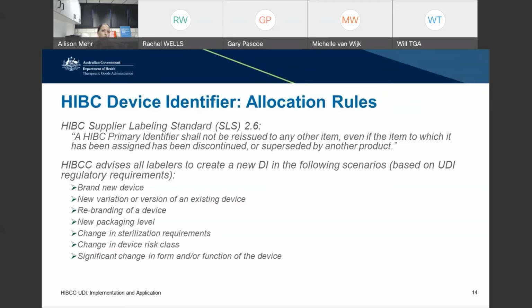So the one allocation rule that is stated in the standard is that the device identifier should never be reissued to another product. HIBCC additionally advises all labelers to create new device identifiers in certain scenarios based on the current regulatory requirements. So, for example, when there's a new variation of an existing device, rebranding or a new trade name, new packaging level, changes in sterilization or storage requirements, a change in the device risk class, a change in the certificate or approval of the device, anything like that. But the general rule of thumb is that a new DI should be created whenever there is a change in form, fit, or function of the device.